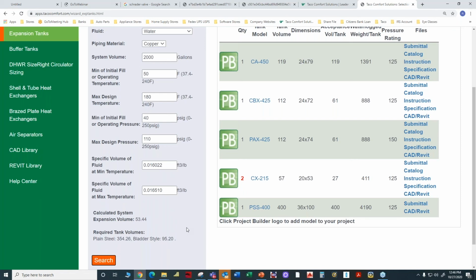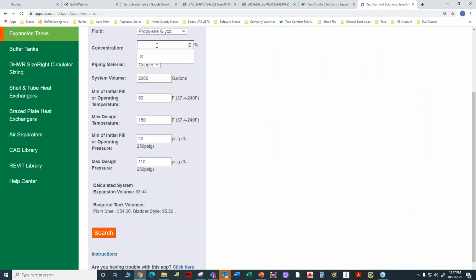And I'll say to them, okay, let's go through the selection process, and I'll walk them through what's on the screen right now. I said, now let's just reconfirm. Did you fill the system with water? And they said, no. It was always supposed to have propylene glycol in it at 50% concentration. I said, well, the selection was based on water. Let me show you what happens to your existing installation if you put in propylene glycol at 50% concentration. So I'm going to change the fluid from water to propylene glycol, change this to 50%, click on search.